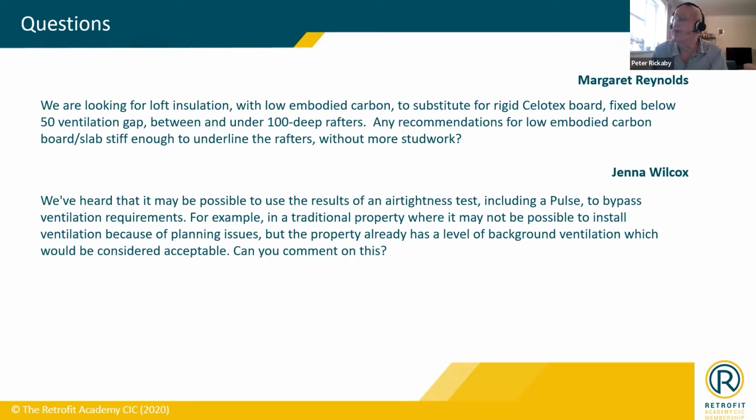We also, in the amendment to PAS 2035, which was published in January, did add a line that said that part of the process of insulating the building is deemed to be making it more airtight, not less. So using more leakiness to avoid doing ventilation is completely perverse from the point of view of the direction in which we're trying to take the building stock, which is towards build tight, ventilate right.